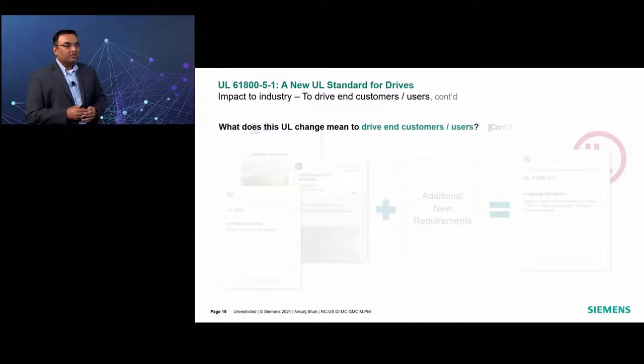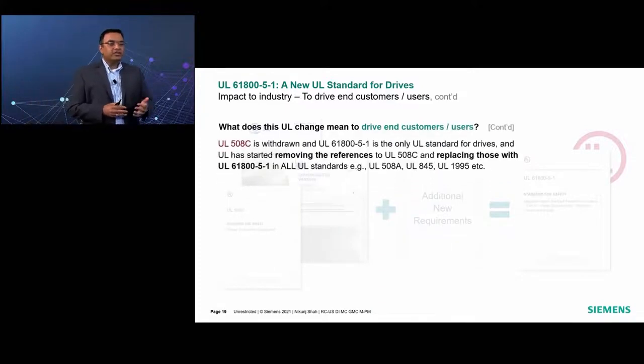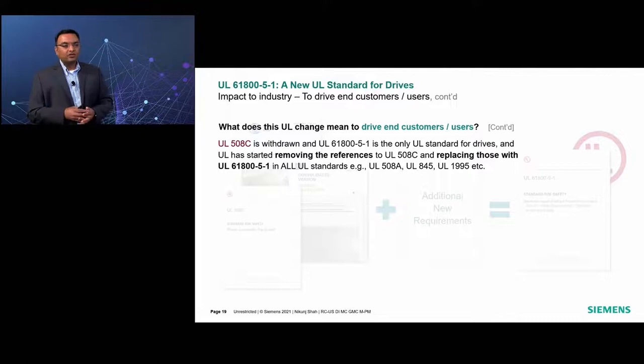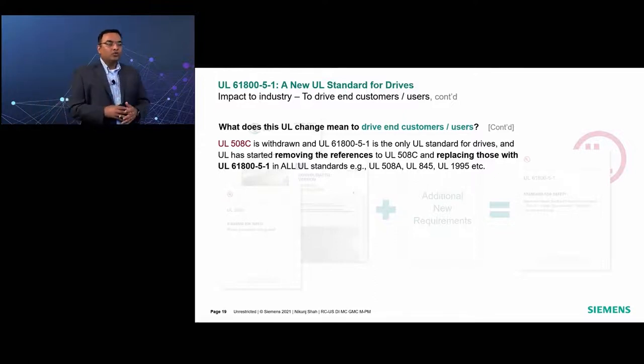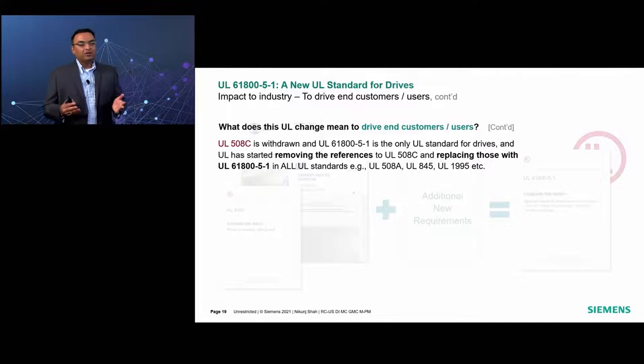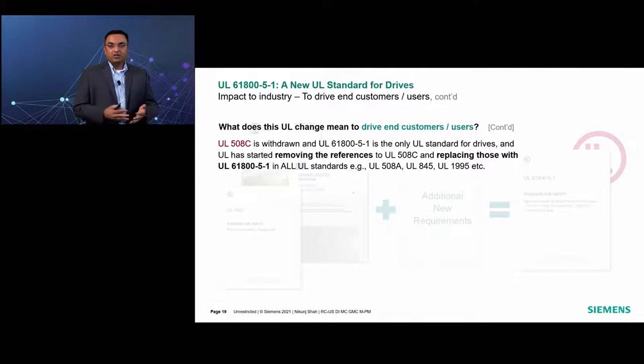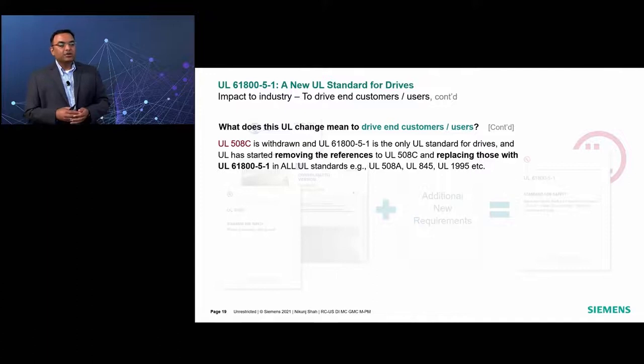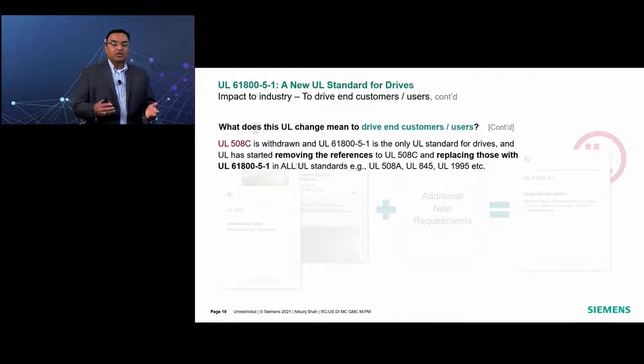Also, as I mentioned earlier, UL 508C is withdrawn last year and replaced with 61800-5-1. And therefore, UL has started replacing the references to UL 508C in almost 80 different UL standards and documents with the new reference 61800-5-1.